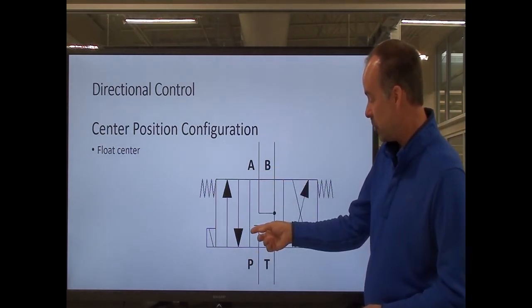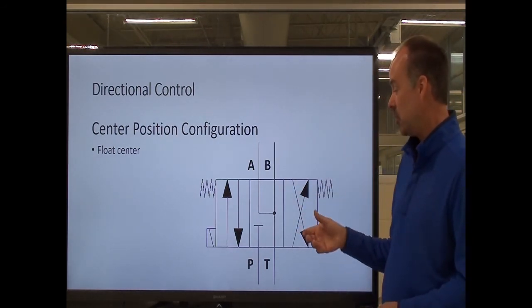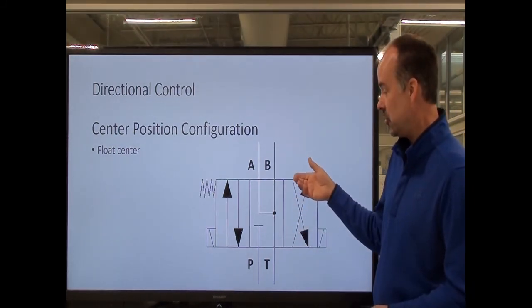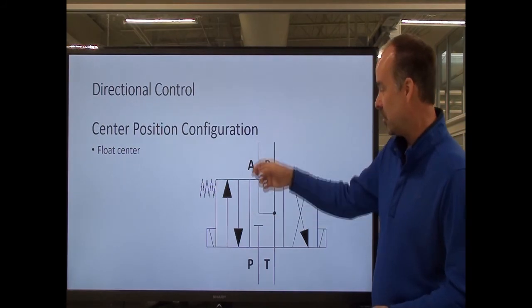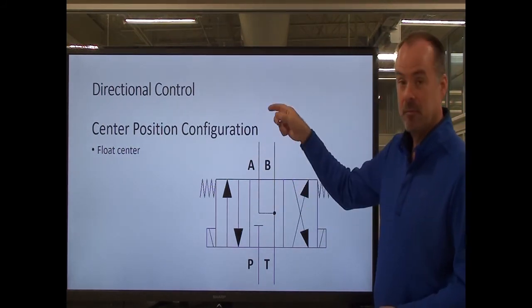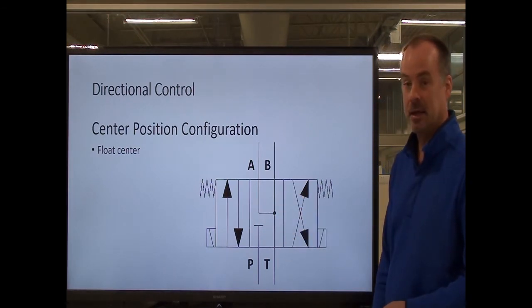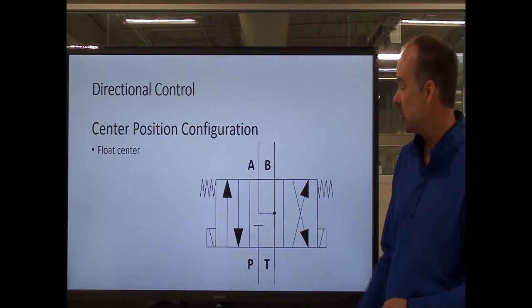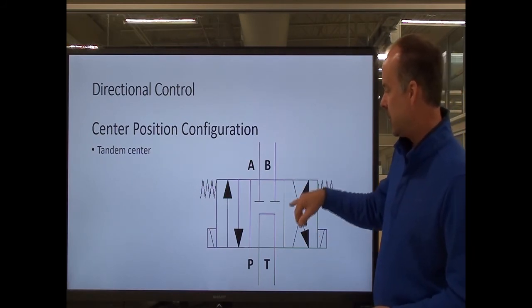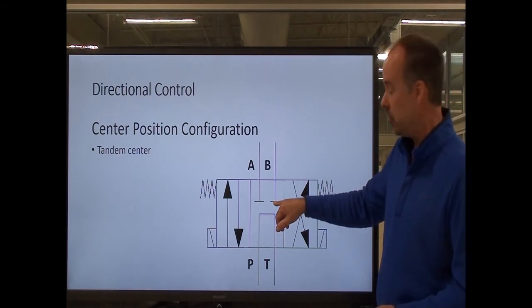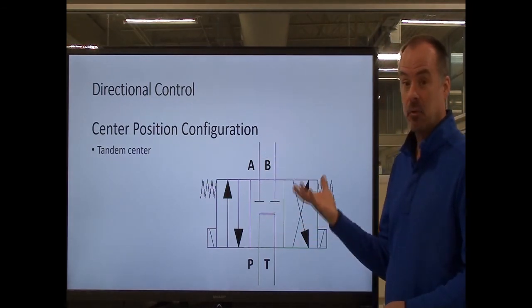The float center blocks the pressure port but ties A and B together back to the tank. This allows an actuator to float in the center position. For example, with a double-action cylinder, you could actually grab the cylinder and slide it in and out because the two ports are tied together, allowing fluid to flow between the two ends of the cylinder. Tandem center is similar to open center, except the actuator ports are not open — pressure dumps straight to tank, but whatever actuator is connected will be locked and not allowed to move.